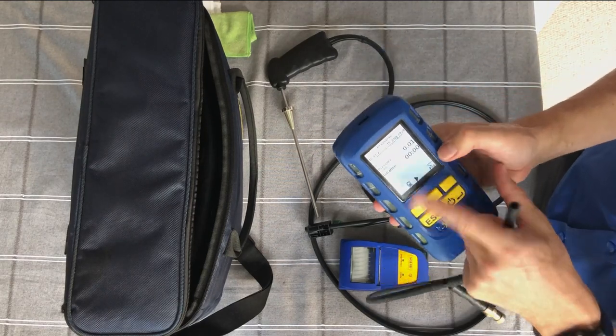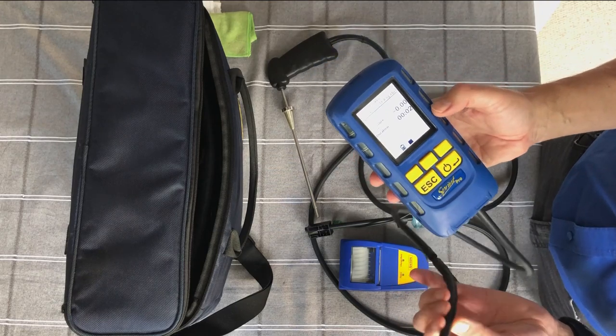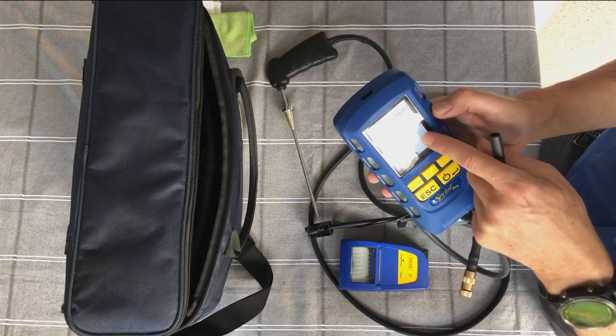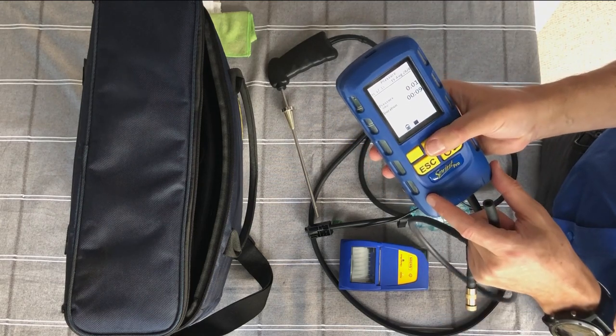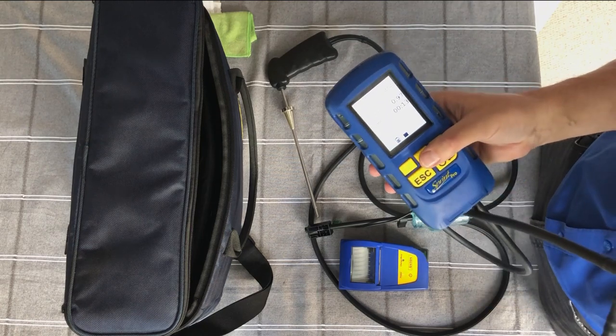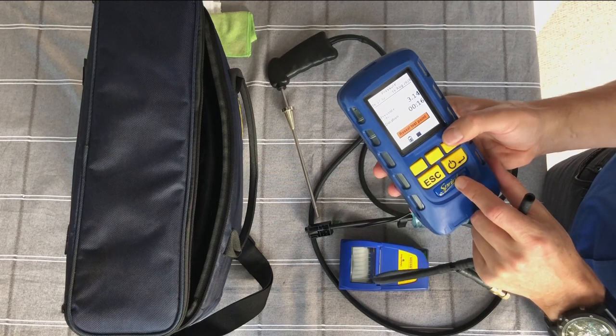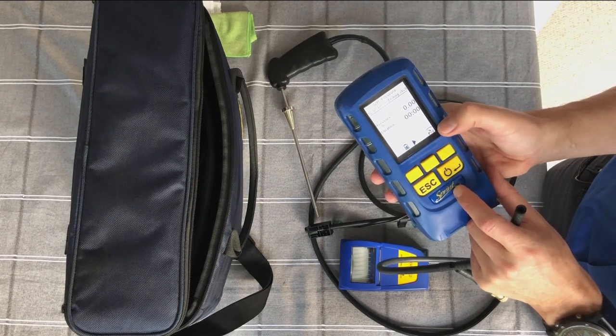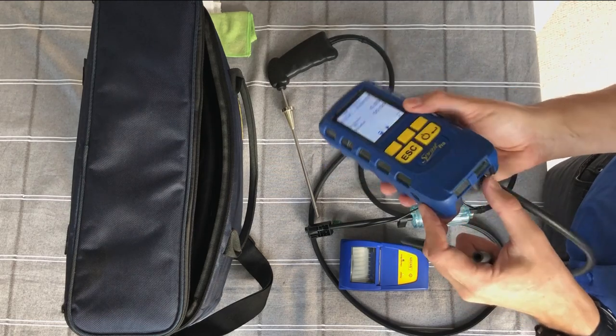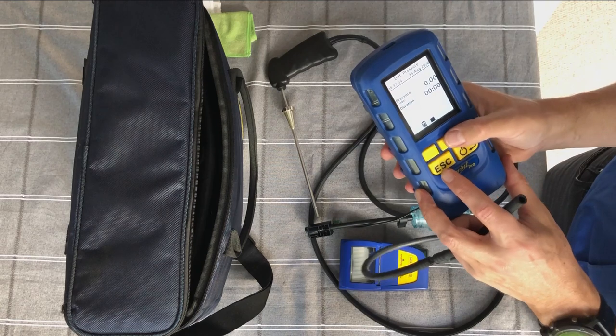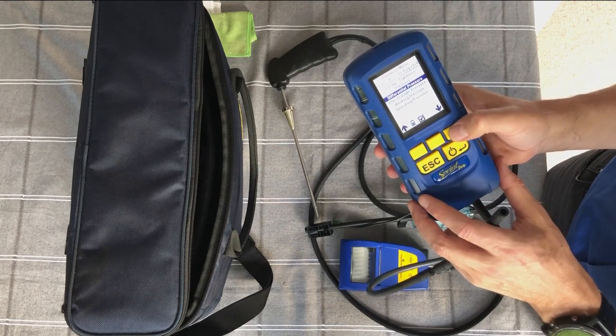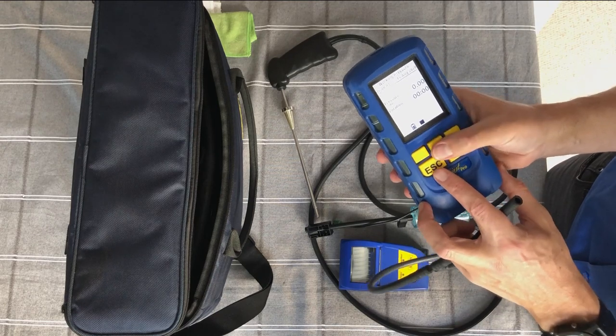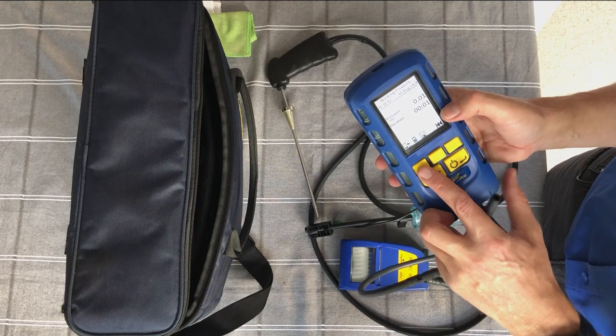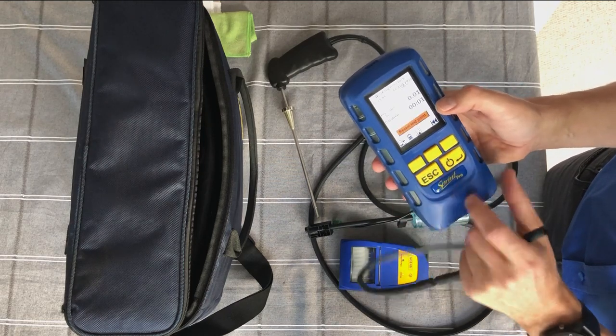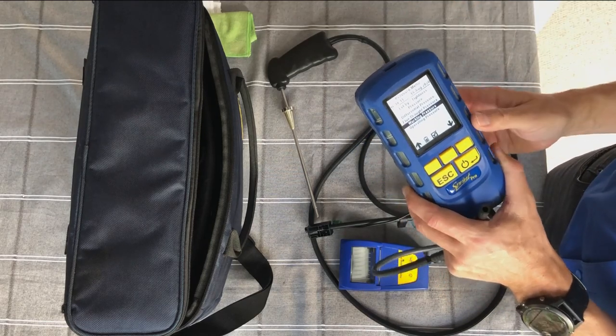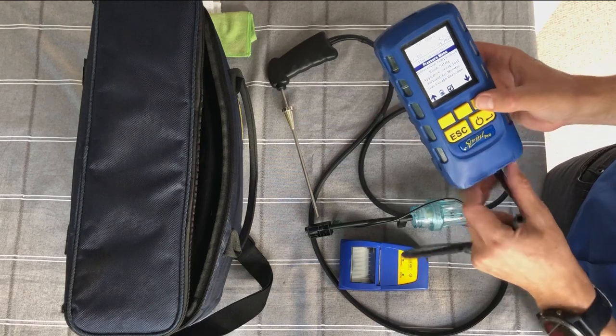If you go into just the pressure, that's just a live reading, so it's basically like using a U-gauge, but it's a digital version. It just gives you a live pressure, and it tells you how long you've been taking the pressure test from when it started. If I blow on it, it just gives you a live reading. If I go down to differential pressure, you need two on there, you hit start, and you can measure that. Then draft pressure, working pressure, it's all fairly self-explanatory, but with the working and operating pressures you can save it as a log. You can print it or Bluetooth it, so you get a specific ticket that says working pressure or operating pressure, whichever you're doing.